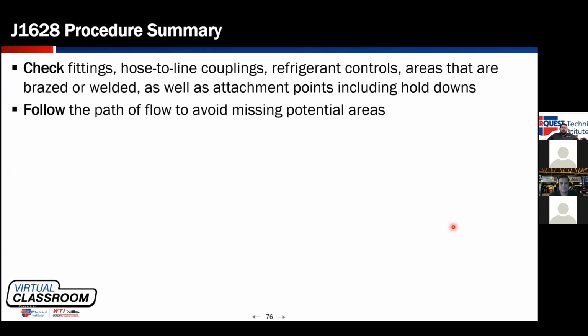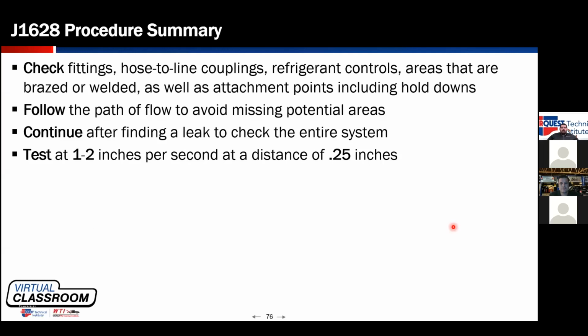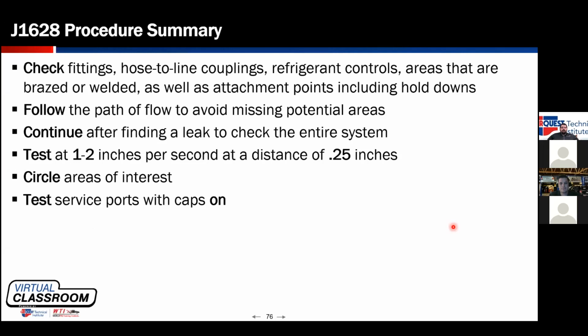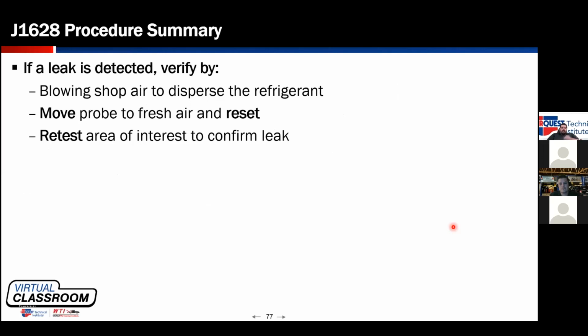Start at a point in the refrigeration circuit and work your way back around to that point to find the leak. Be close to the system with the detector, moving slowly around the system. And service ports we need to test with the cap on. Remember, with the service port, the cap is the primary seal. If we find a leak, verify it. Clear the area out, go back and retest.